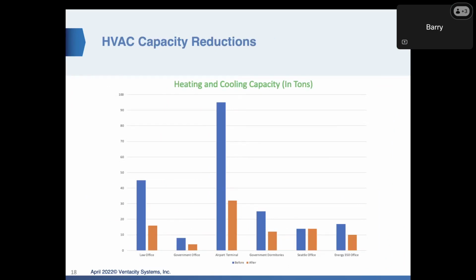Here is the heating and cooling capacity, before and after, on those same projects. So we took 46 tons of rooftop units off and replaced it with 16 tons of VRF. So very consistently, we've reduced that capacity by close to 50% or better in most of these projects.